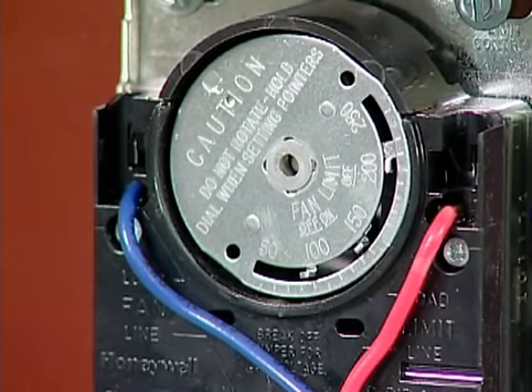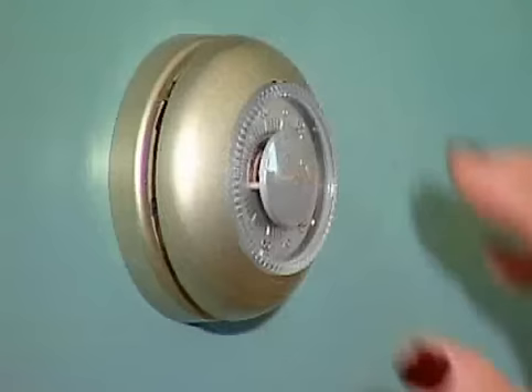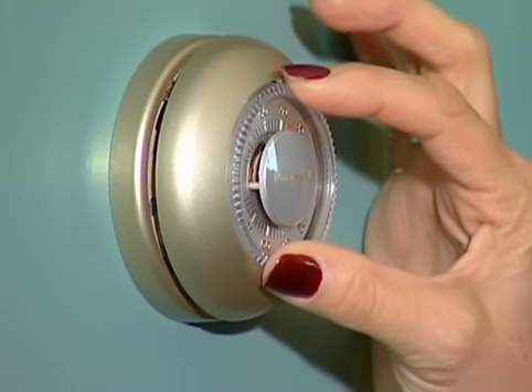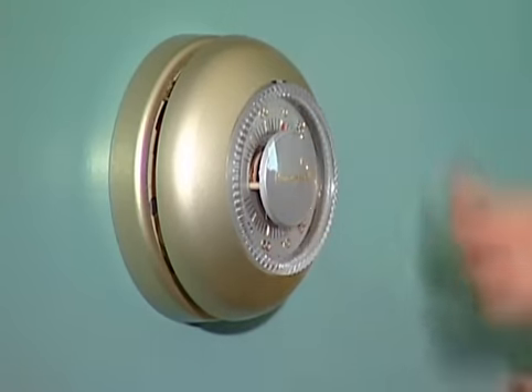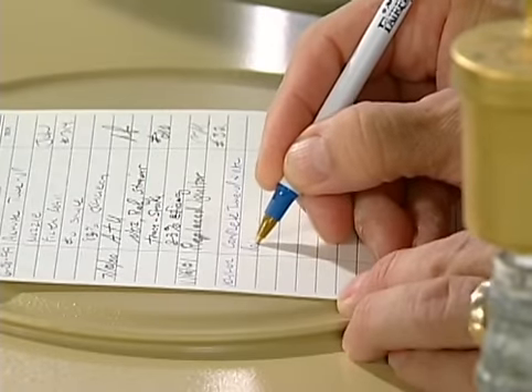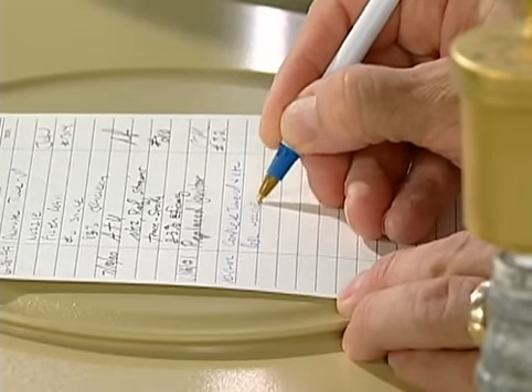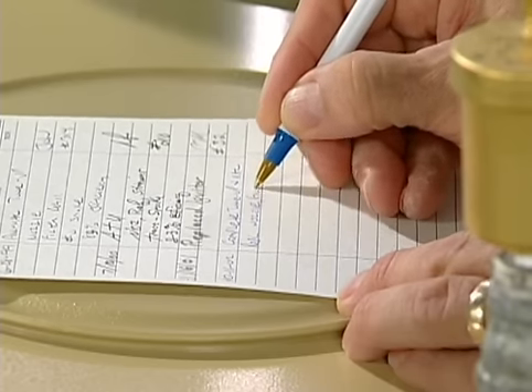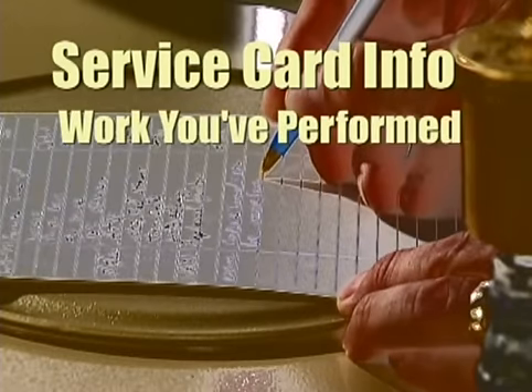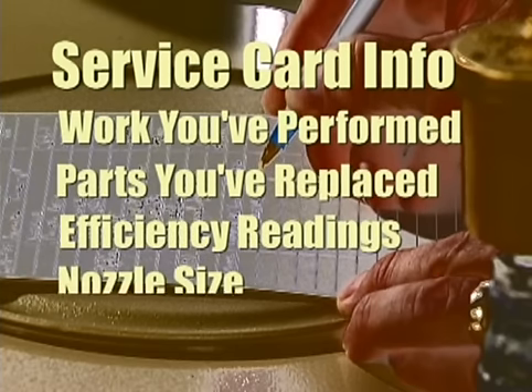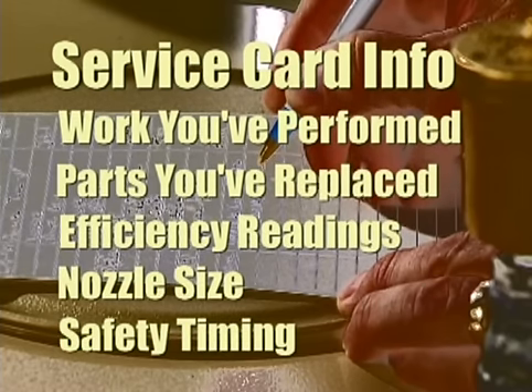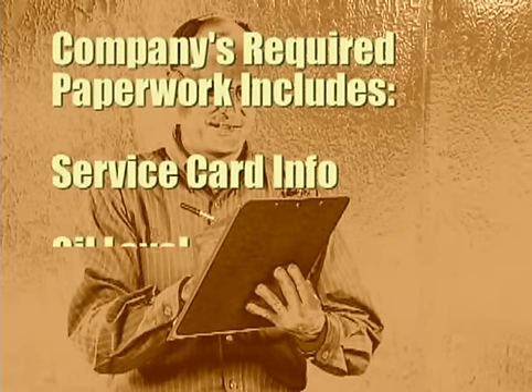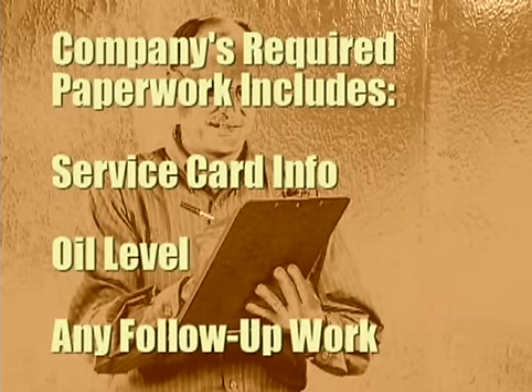Verify that the high limit control is operating correctly and all controls have been returned to their proper settings. Ask the customer to reset all thermostats to their normal settings and make certain the system is working properly. Fill out the service card completely so that on future visits the technician knows exactly what you've done. Include the work you've performed, the parts you've replaced, the efficiency readings, the nozzle size, and the safety timing. Fill out your company's required paperwork completely, including all of the information on the service card, plus the oil level and anything that needs to be followed up on.